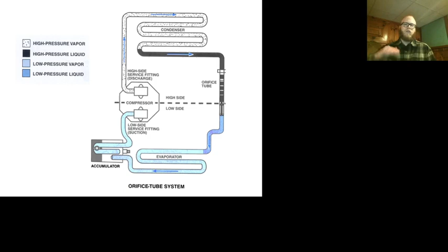Well, if we get to the point where the system is cooled as well as it possibly can, to the point where we're worried about getting liquid into the compressor, or if we're worried about lowering the temperature of our evaporator so far that we start to ice up the outside of it, because we're trying to stay right around 32 degrees in that evaporator so it works as well as it can, but that's also the point at which water freezes, so we've got to stay just north of that freeze point. Well, the easiest way to control this system is just turn it off.